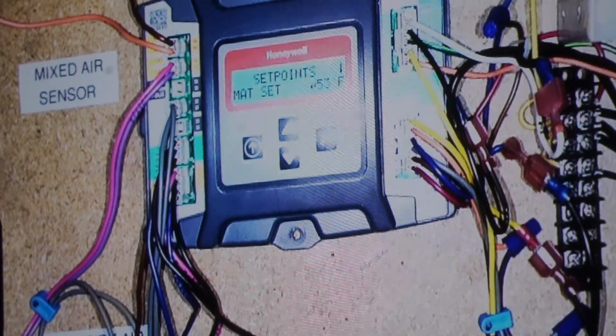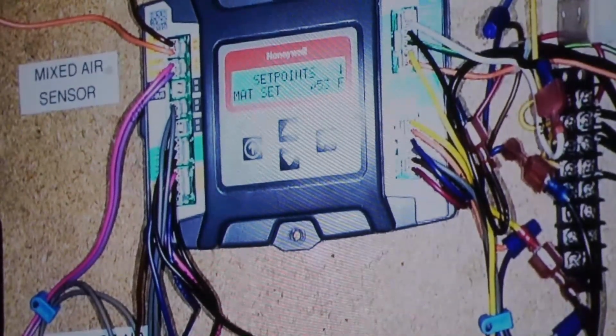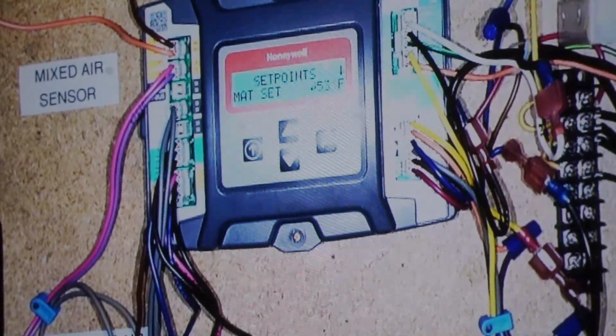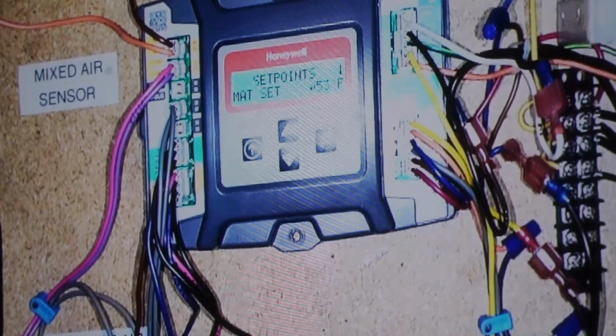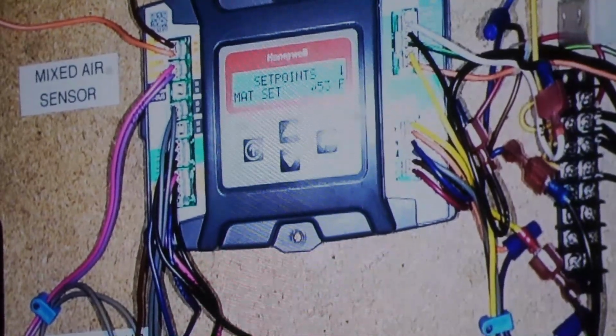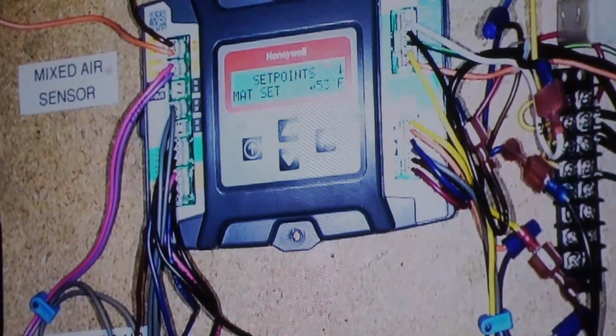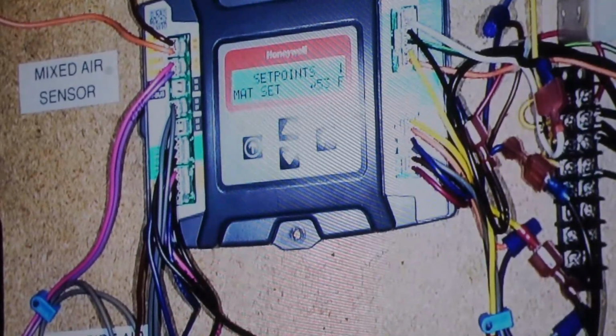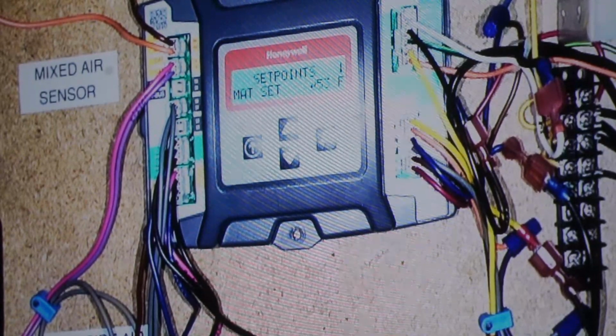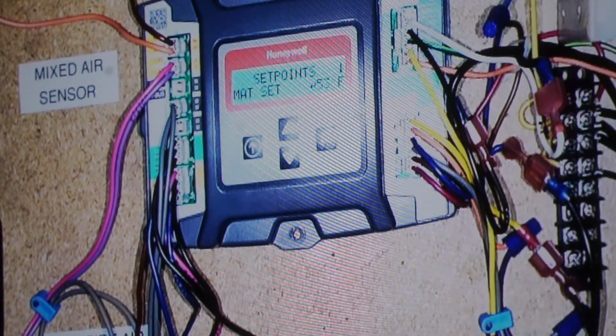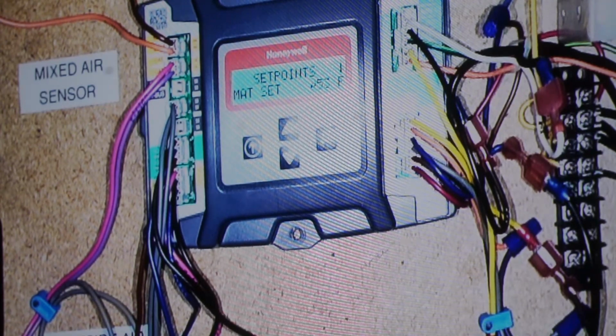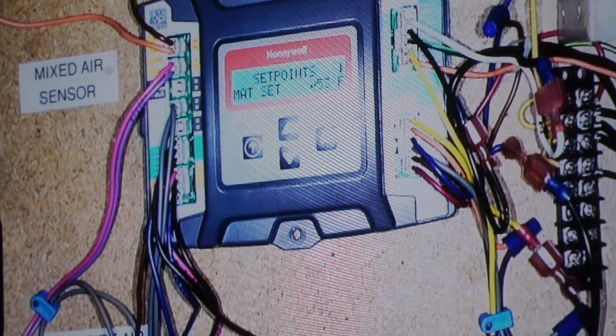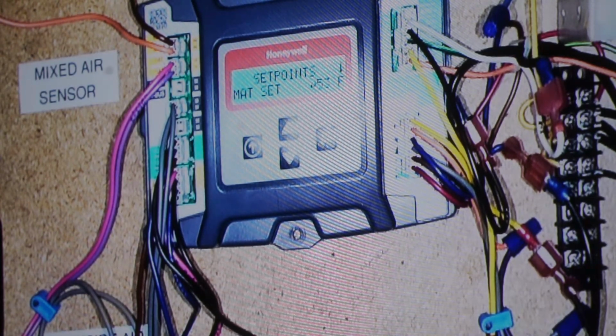So like more cold air, think about when this diffuser was running back in the day. 55 degree air, this is an induction style diffuser, so it supplies air, but it's also mixing return air in and induces return air. And if it's a 10-to-1 diffuser, for every 100 CFM of supply air, it's moving 1,000. This isn't 10-to-1, but that's just easy math. Fun facts, if you see dirt along a supply air register, and they say, hey, your unit's messing up our space, you're politely saying, no, your space is dirty, because the return is getting engulfed in that supply and leaving its dirt on the ceiling tile. So no matter how many filter changes you do and how many coils you clean, you're not cleaning up that ceiling tile if it's got those marks. It's coming from the space.